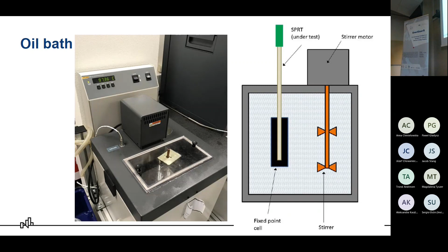This is the oil bath where the fixed point cell is submerged. We use the stirrer to have the same temperature exactly at every single cubic centimeter of the oil bath. And HSE rules are very important: health, safety and environment. Silicone oil has these properties that formaldehydes are formed when the temperature of silicone oil is greater than 150 degrees. So you have to be very careful. The breathing mask with fresh air supply, hazardous material suit and safety gloves are required.